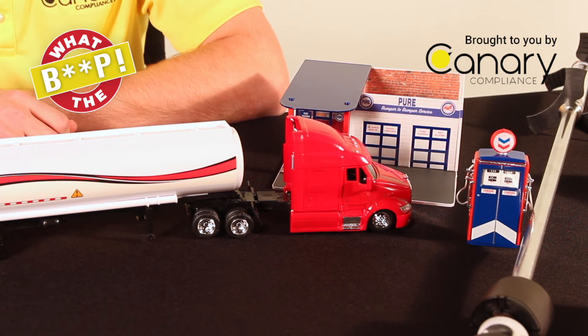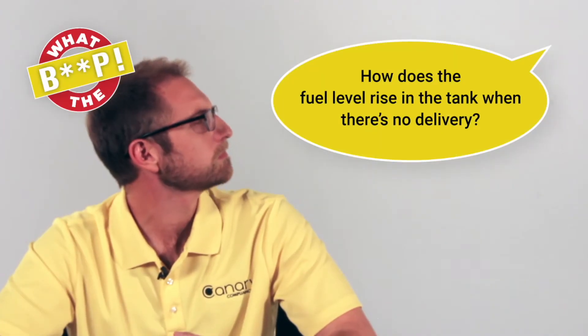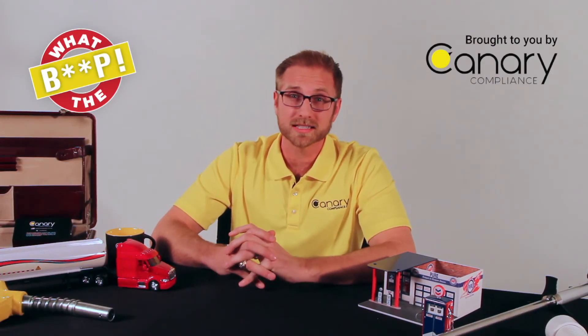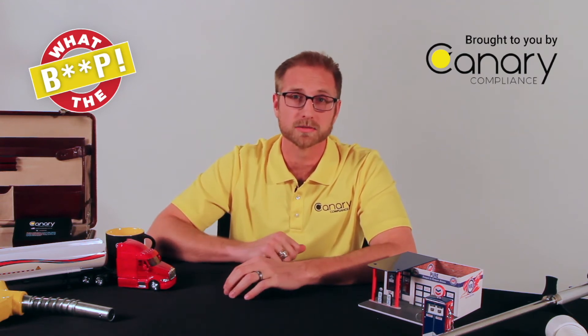The CSLD rate increase warning occurs when the volume in the tank rises unexpectedly without a delivery. How does the fuel level rise in a tank when there's no delivery? Maybe water's entering your tank — and that's not good. Fuel and water don't mix, and if a customer gets that in their car, you could be on the hook for those maintenance bills.